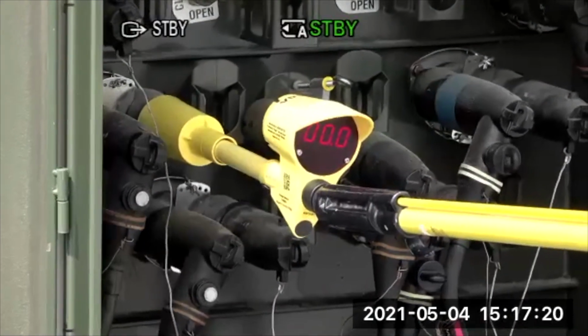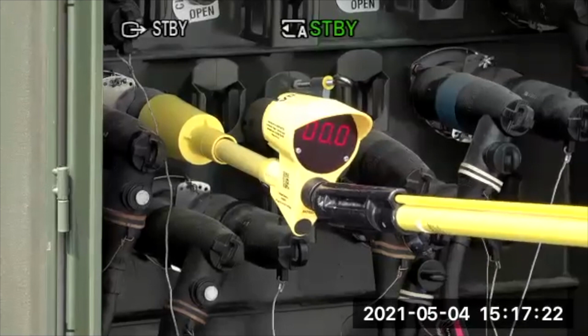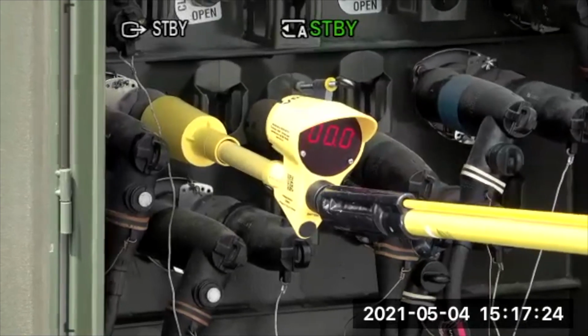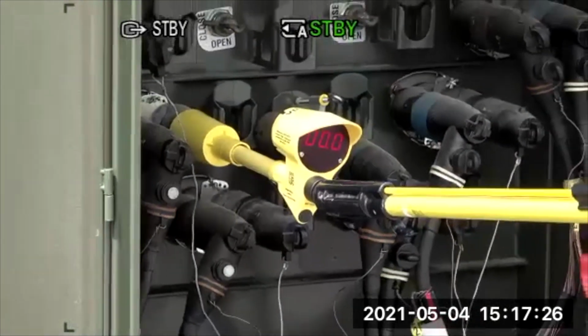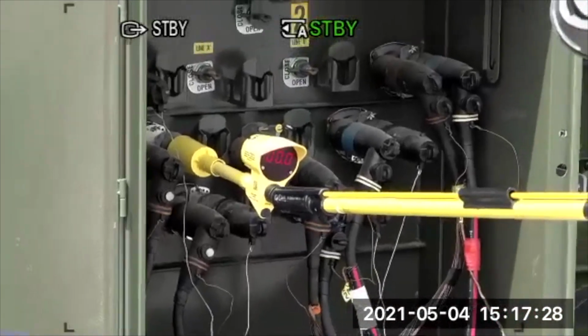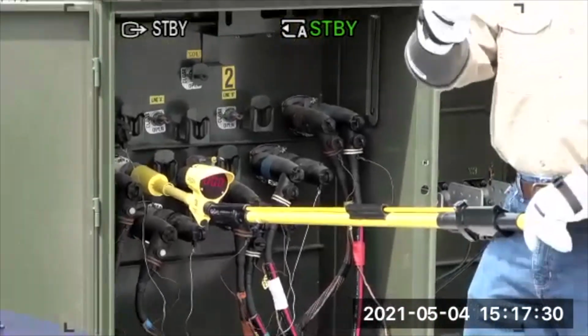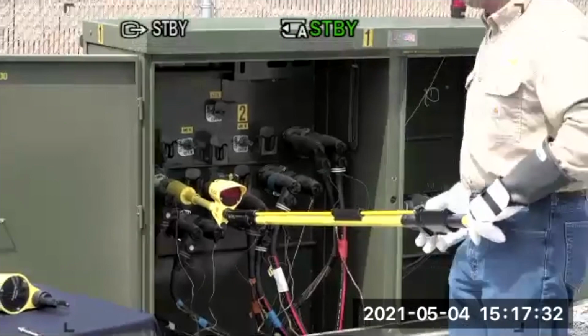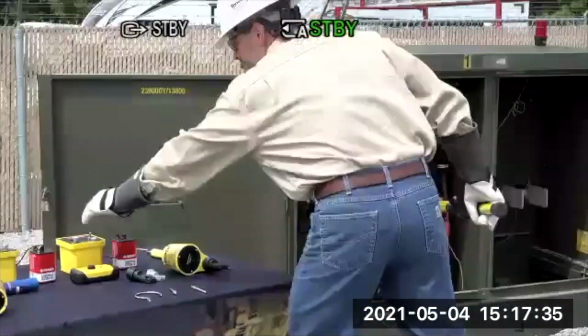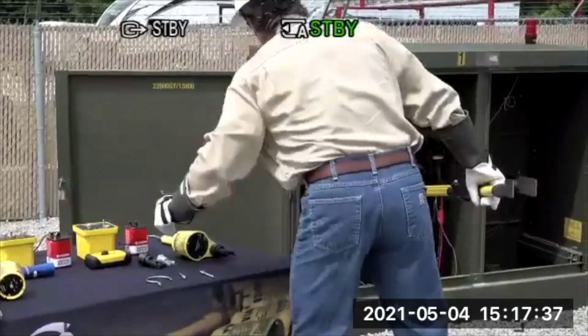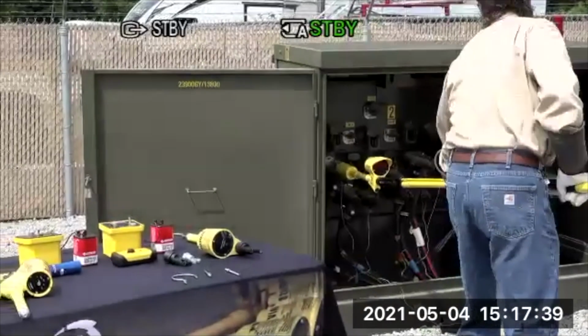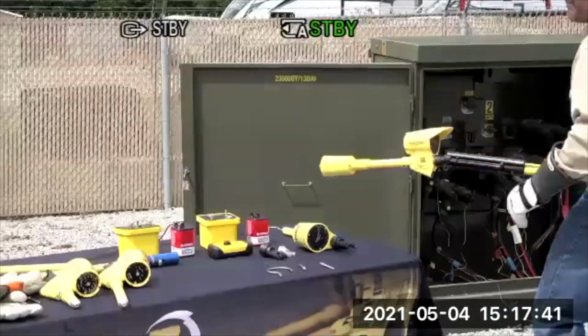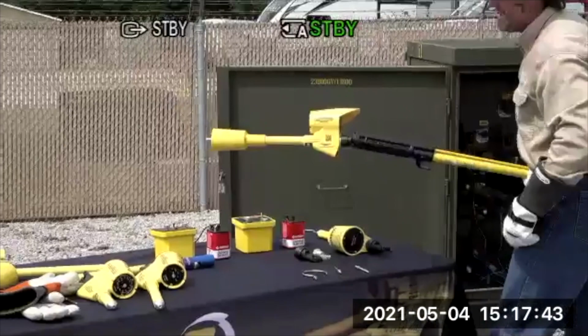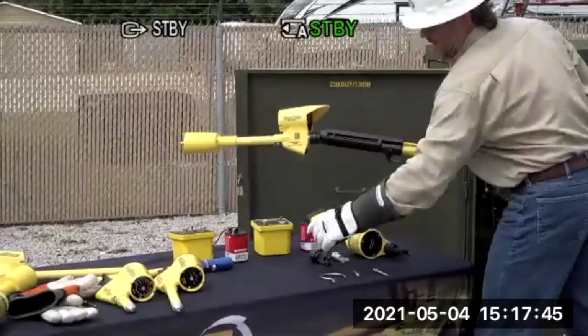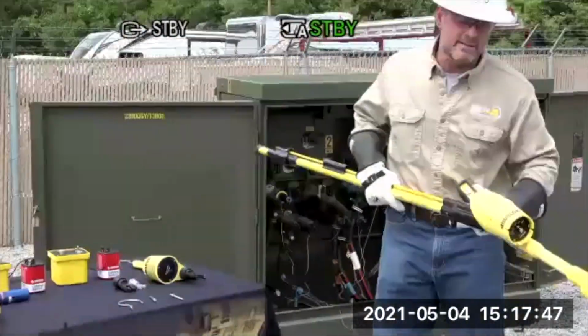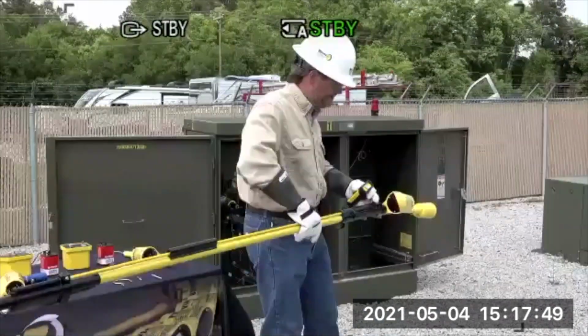So a lack of all 3 voltages prior to putting on our temporary grounds. Now what we're going to do is, we tested, we opened, we tested, but now we're going to test the tester. We have a 3 kV power supply we can test our tester on, and we also have a new handheld power supply that we're going to test our tester on.